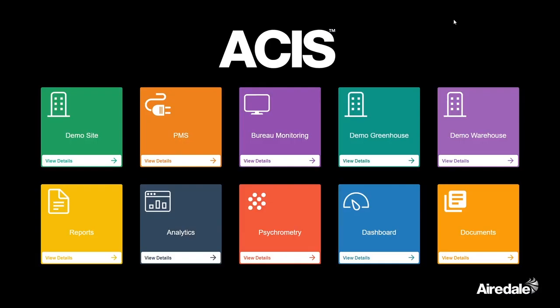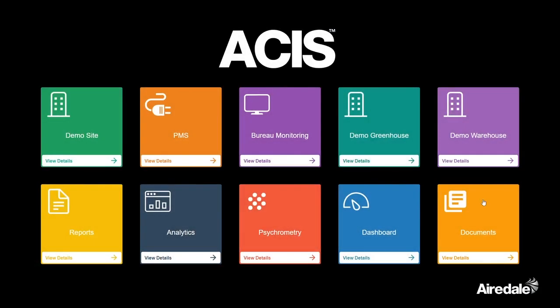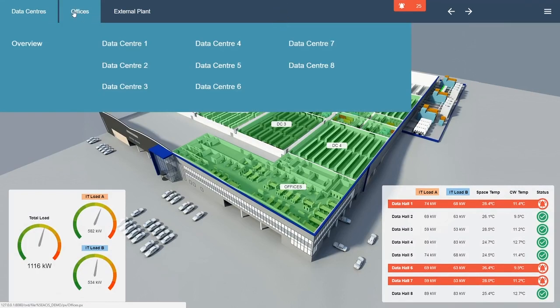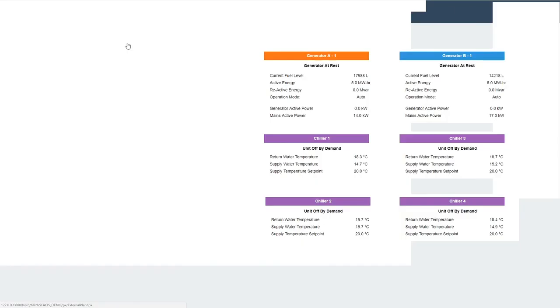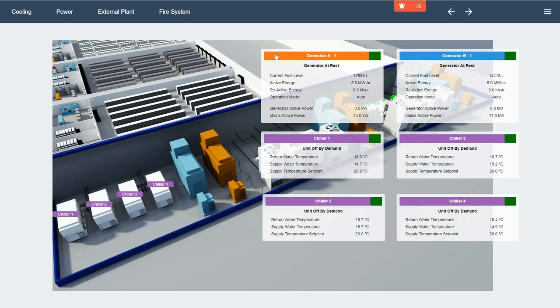What we're showing today is what we call ACIS controls, which is Airedale Controls Integrated System, which is a system developed in the UK, and it's something that we used over there for data centers and large building management systems. So we're not just integrating unit heaters. This system has everything from the data center to the offices, the external plant, the cooling, everything is all built into this system. And I think the good thing to say about this is now we've got a very large system, and now you can even tie a unit heater into that large system. It's something that you couldn't do before.